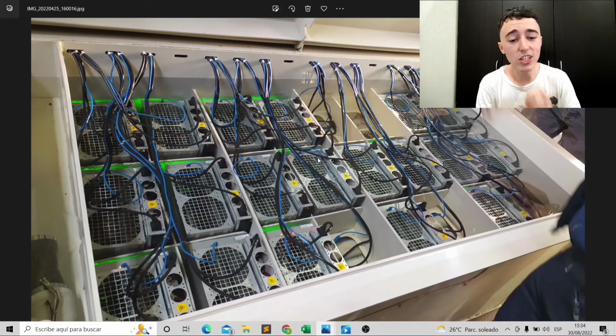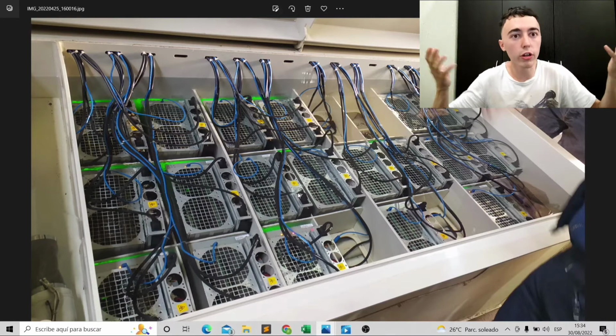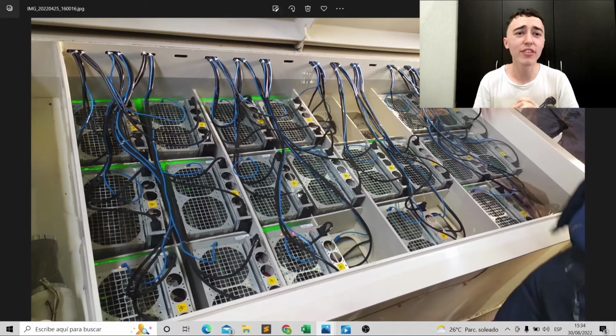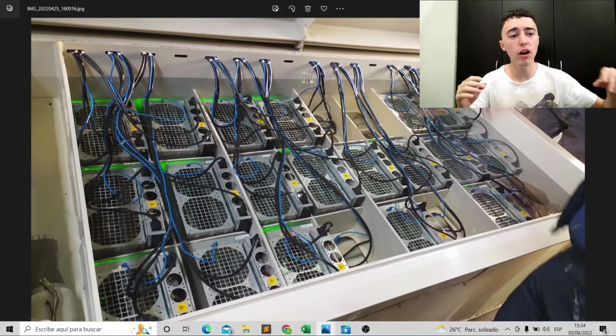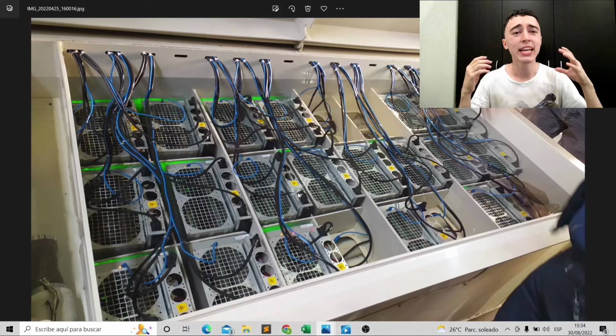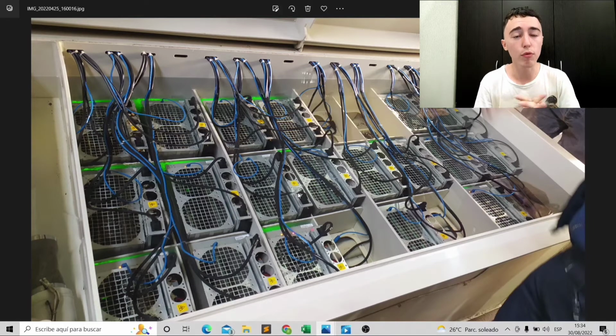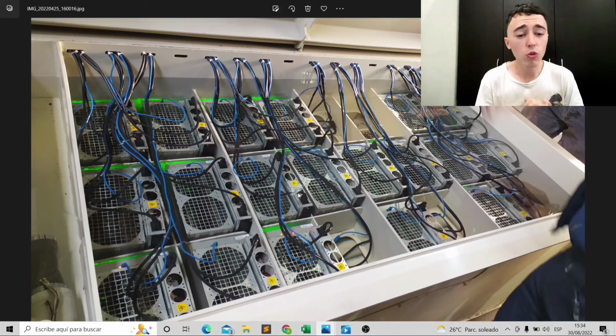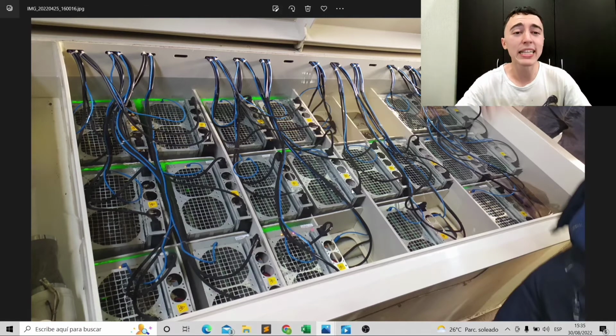Is it a good idea? Well, it's true that the most important part is it's more stable, way more stable. ASICs, if you have one outside with air cooling, normal cooling, around 1.5 to 2 years after you start using it, if the ventilation isn't filtered and you have dust on it, the ASIC becomes less stable. But if you put it in this immersion cooling solution, it's much more stable. It stays stable much longer, at least 2 to 3 years, or even 3.5 years. Immersion cooling works pretty good, but it does have one problem.